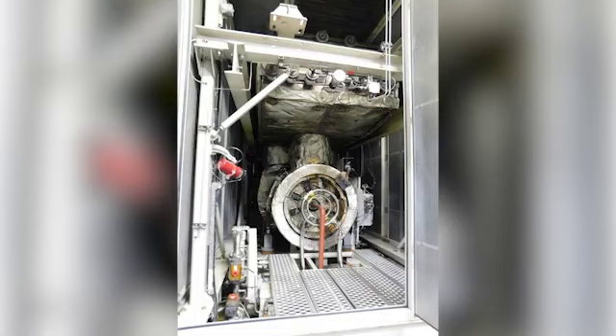We'll take a quick peek inside the gas turbine because it is a very interesting engine. The Mercury 50 is an ultra low emissions engine. We're doing 4.6 megawatts at a very predictable and consistent 4 ppm NOx, and with a barely discernible CO. And this is just a remarkable engine. It has a recuperator on it, which takes the exhaust energy and passes it to the compressed air after it leaves the compressor on the turbine and before it's sent into the power turbine and combusted. So it does that extremely well, and again, very consistently.